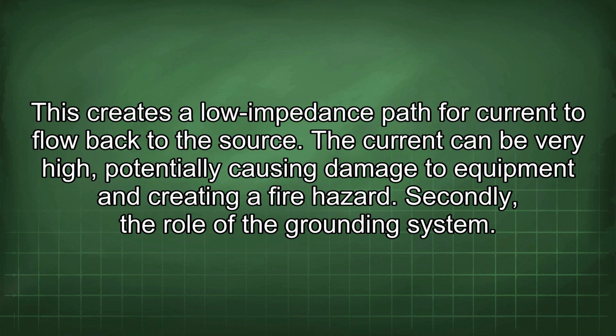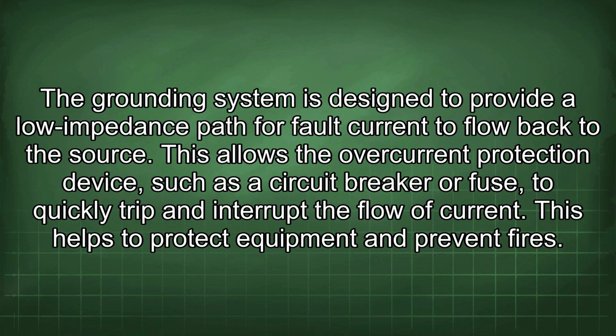Secondly, the role of the grounding system. The grounding system is designed to provide a low impedance path for fault current to flow back to the source. This allows the overcurrent protection device, such as a circuit breaker or fuse, to quickly trip and interrupt the flow of current. This helps to protect equipment and prevent fires.